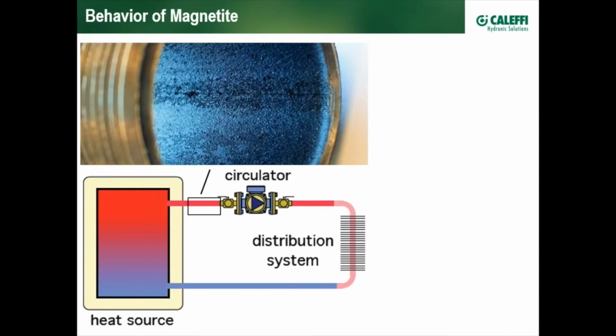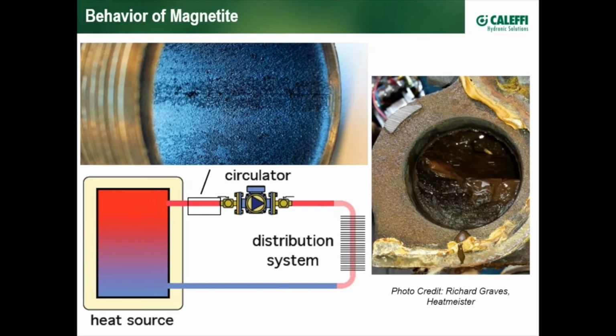How is magnetite formed? I mentioned a little bit of oxidation. So take a black pipe, 1-inch diameter in this example. If it's exposed to oxygen, debris starts to build up, flake off, oftentimes microscopic. It floats around, driven by the circulator. As the circulator turns off, it settles to the bottom somewhere in the system. Circulator kicks back on, floats around. Over time, though, much like flour on a counter, left there long enough and able to be blown off with your breath, it will cake up and become somewhat solid. Somewhat similar phenomena happens in a system where the magnetite can start caking up, such as was in this section of a boiler that cracked as a result of magnetite caking up.